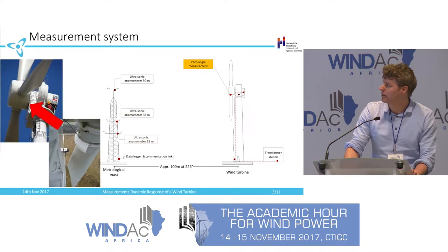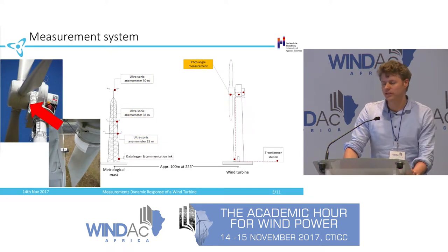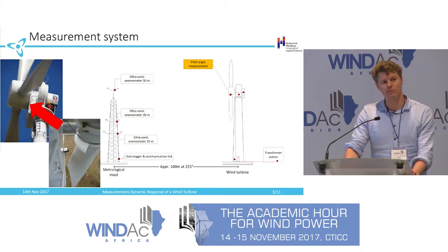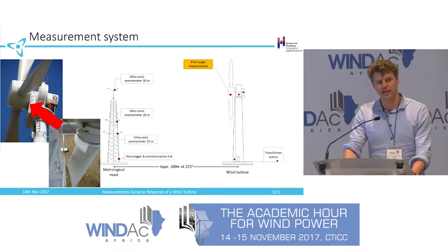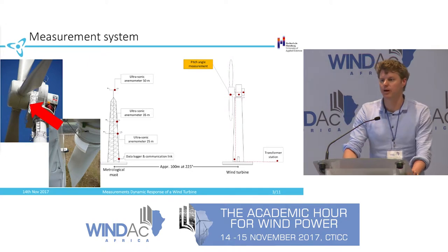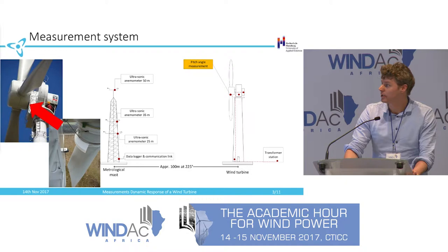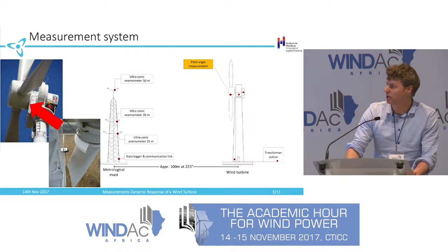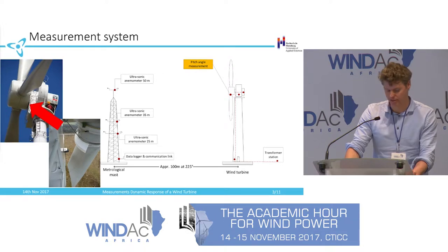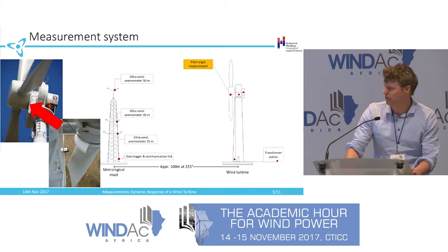Second thing that's very important is the pitch angle. The problem here was that Enercon didn't want to give us the pitch angle from the SCADA system, so we had to come up with a measurement system on our own. And as it being a retrofit, a colleague of mine designed a contactless pitch sensor, which I think you can also find a publication on in Wind Energy.